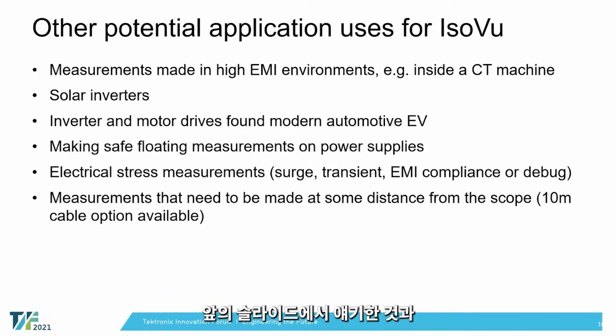Here are some other applications where IsoVu is well suited, along the same lines as before: making measurements in the presence of high common mode, whether from switching relays or, in one example, inside CT machines, which don't get much more EMI unfriendly than that. IsoVu does well rejecting and peering through the common mode noise around the probe. Solar inverters, automotive inverters, and motor drives adopting silicon carbide and gallium nitride topologies are also very well suited use cases for IsoVu.